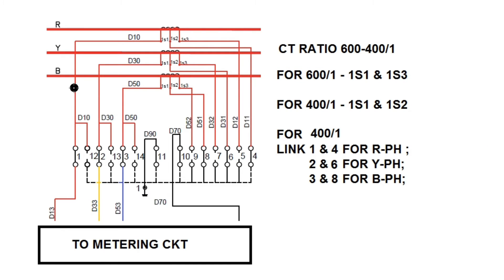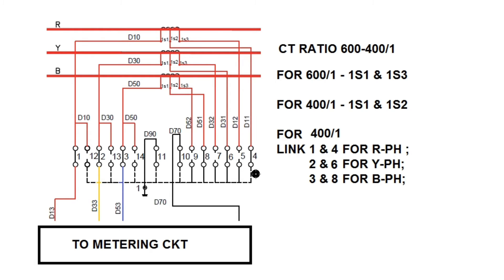Here the CT wiring connection for the metering core has been shown. The TB numbers are 1 through 14. These are the TB numbers taken for the metering core CT secondary circuit. All these TBs are disconnecting type TBs, so we can break the connection between two terminals.